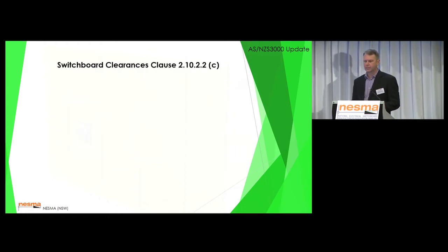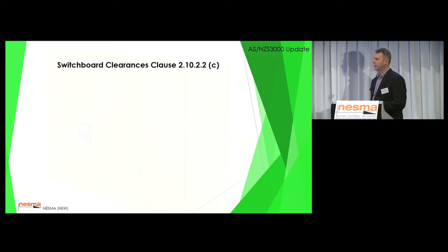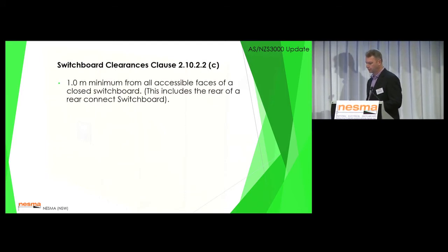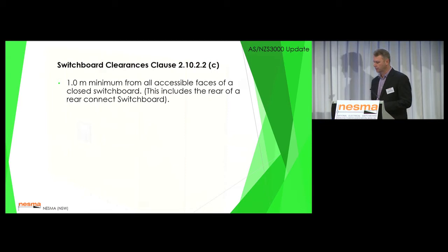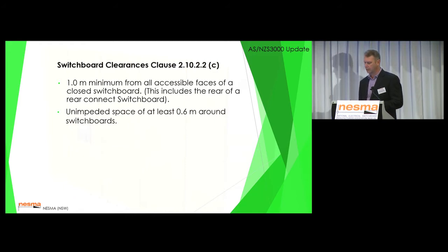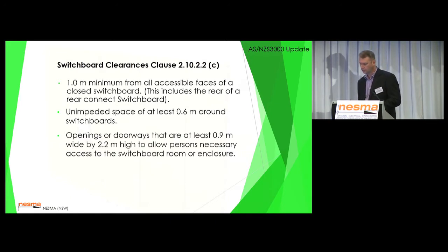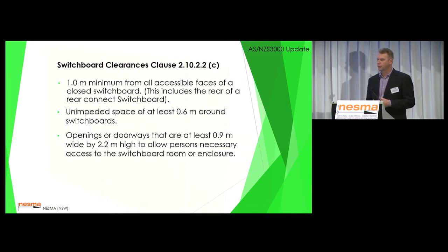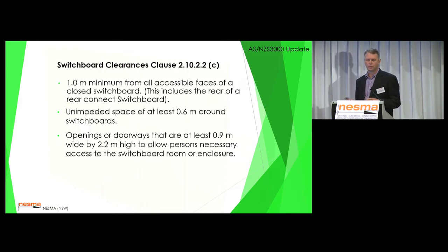So let's start with clearances. This is a fairly significant change for us as switchboard manufacturers and for a lot of the specifiers in the room. There's now a 1 metre minimum clearance from all accessible faces of the switchboards, where it used to be 600. This is not from the sides, this is only from the usable faces. An unimpeded space of at least 600 around the switchboards is pretty much standard as what was in place before. Openings and doorways are at least 900 mm wide and 2200 high. Now that's a big one if we look at the switch rooms these days, where the slab was poured, the switch room was laid out, the switchboard was put in, and then the room was built around it, which makes it very difficult to get these things out.